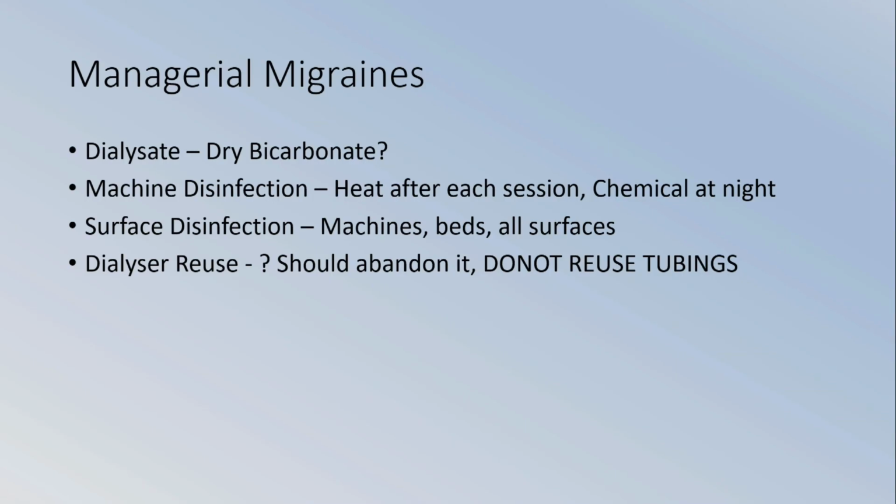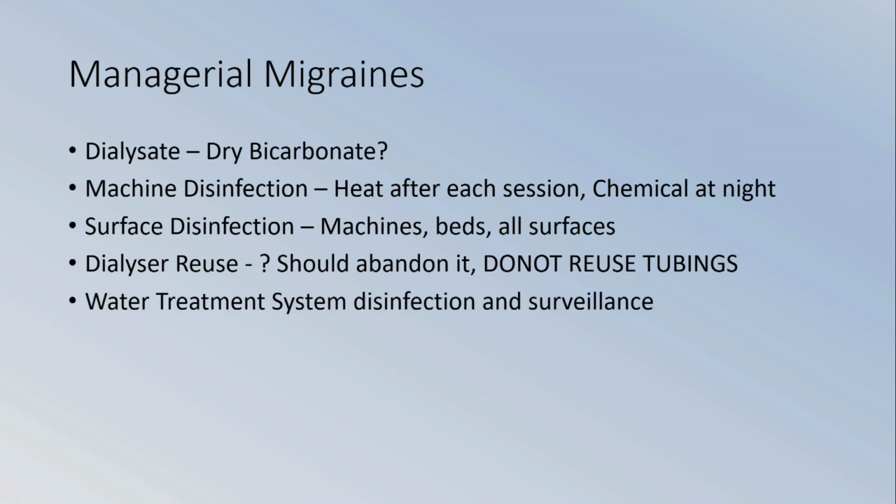But definitely do not reuse tubings. Stop from today. Don't reuse tubings, which cost 120 rupees. There is absolutely no cost effectiveness in using that, because the amount of manpower, water and chemicals that you use to reprocess a tubing is just not worth it. Just pass that 120 rupees on to the patient and they will be happy to take it.